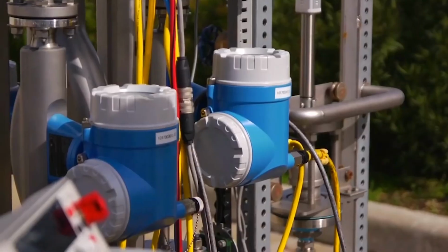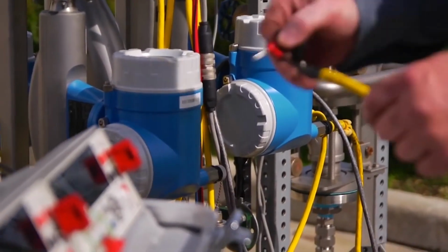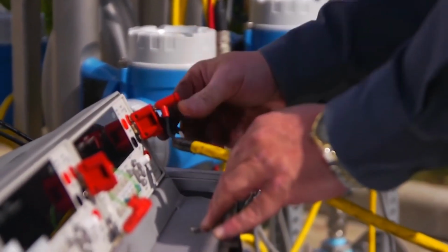We offer different types of calibration. You'll hear it referred to in the industry as standard calibrations versus accredited calibrations. So it depends what the customer needs, what their process or their industry is looking for. Our on-site options, we can calibrate up to a 3-inch meter in line, or we can do a 2-inch meter with our lab rigs.